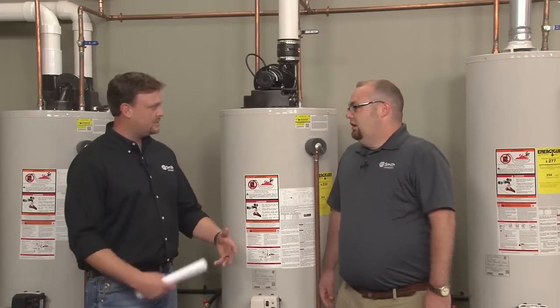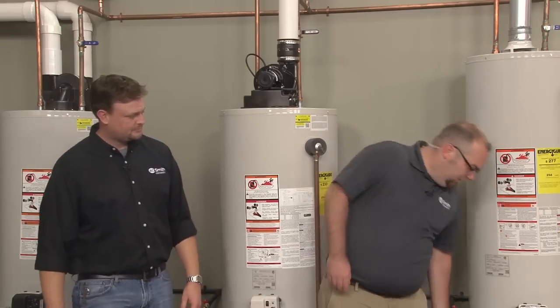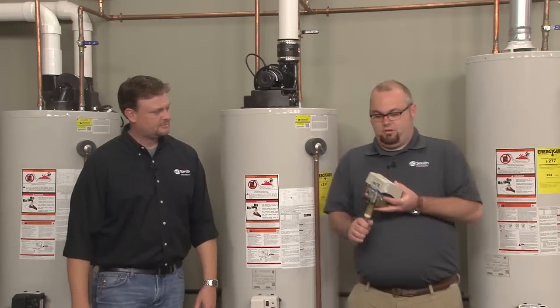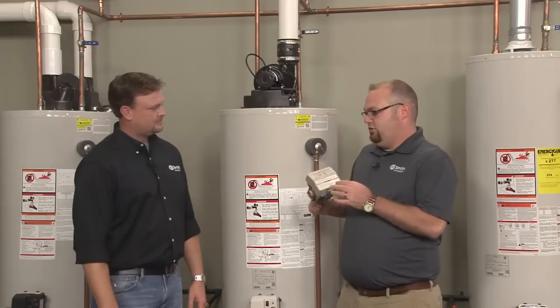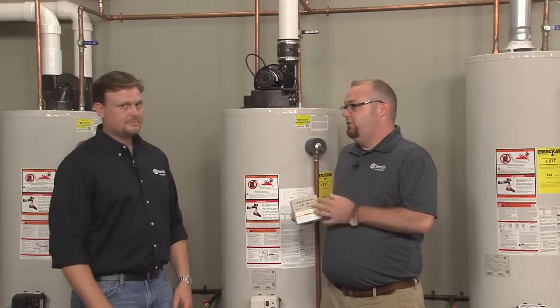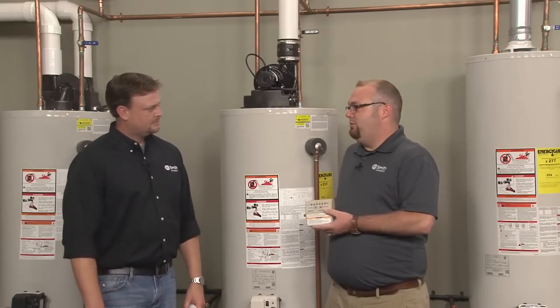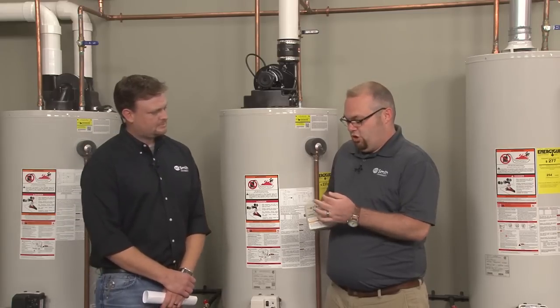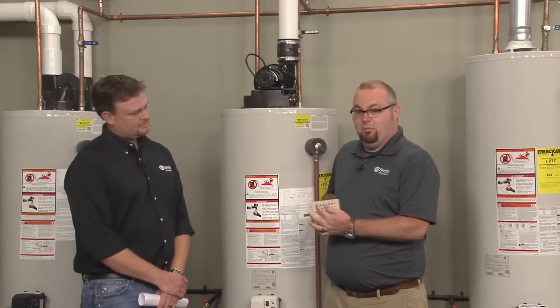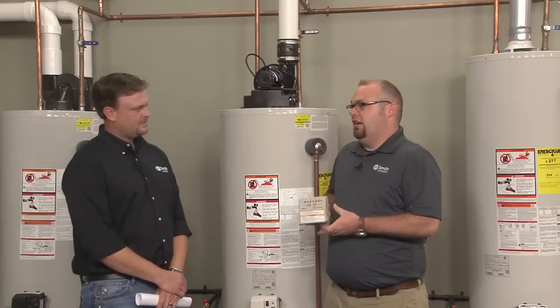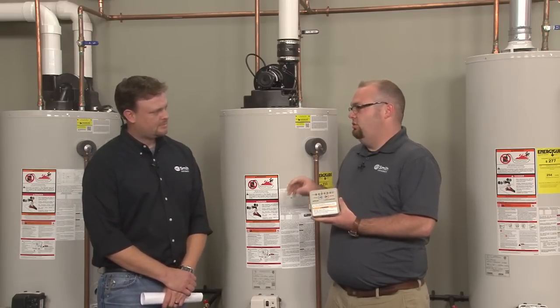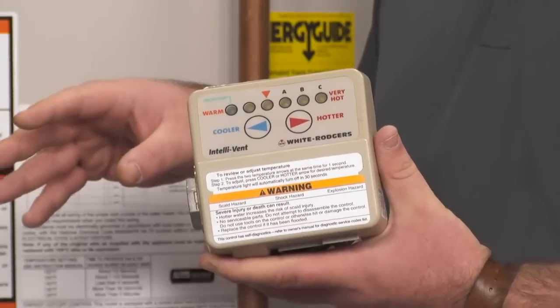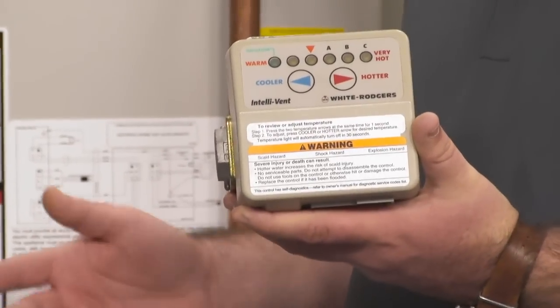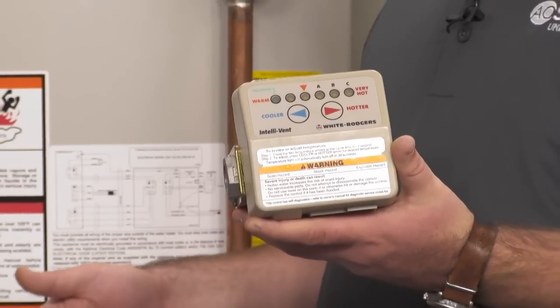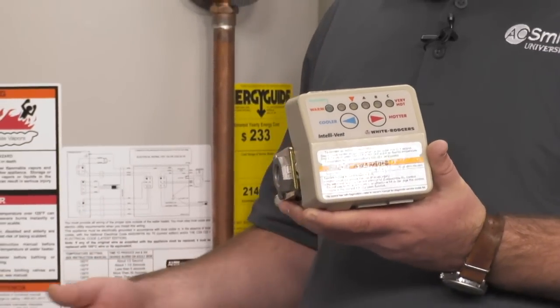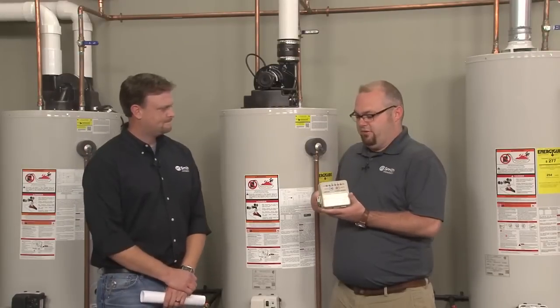Now on the IntelliVent, is there anything different on that? On the IntelliVent, yes, it's different. Of course, the codes signify differently because we have a different way of delivering codes. So in the IntelliVent, the flammable vapor lockout code is going to be shown by the first light being illuminated and the last light. Okay. Now you can turn the heater off, turn it back on, the code's just going to immediately pop back up. So same thing, check around, make sure nothing's flammable, right? If you do see something flammable, remove it, air out the room, all that good stuff.